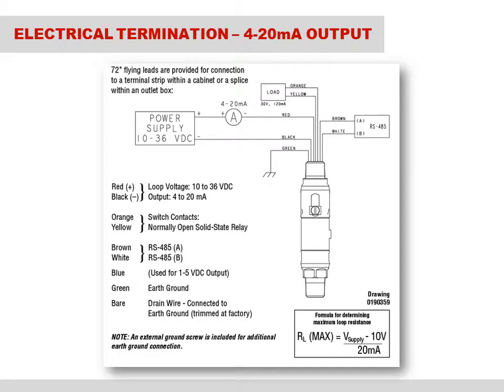All variants or flavors of the 815 PT Smart Pressure Transmitter will have 8 color-coded insulated conductors or wires, also known as flying leads. The 8 colors are, in alphabetical order, black, blue, brown, green, orange, red, yellow, and white. All 8 conductors do not need to be terminated or wired. It is okay to use only the wires that are required for your specific application.